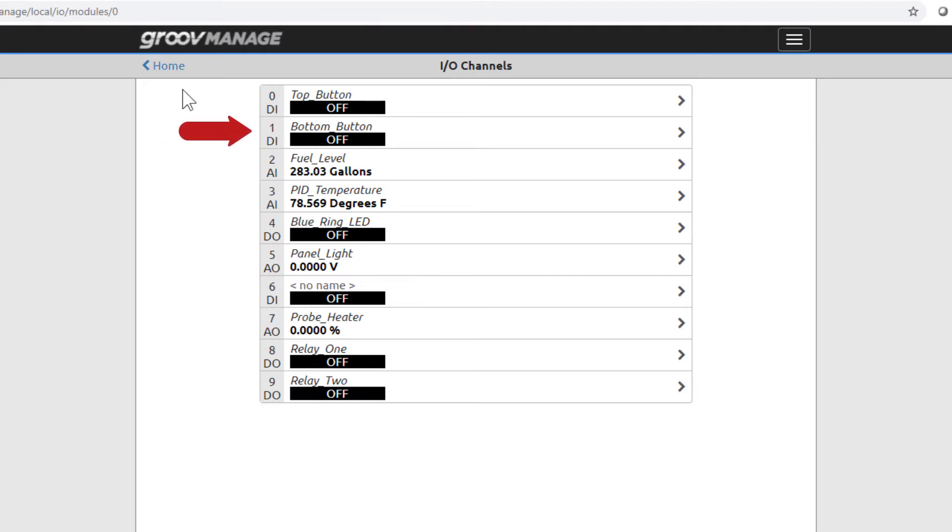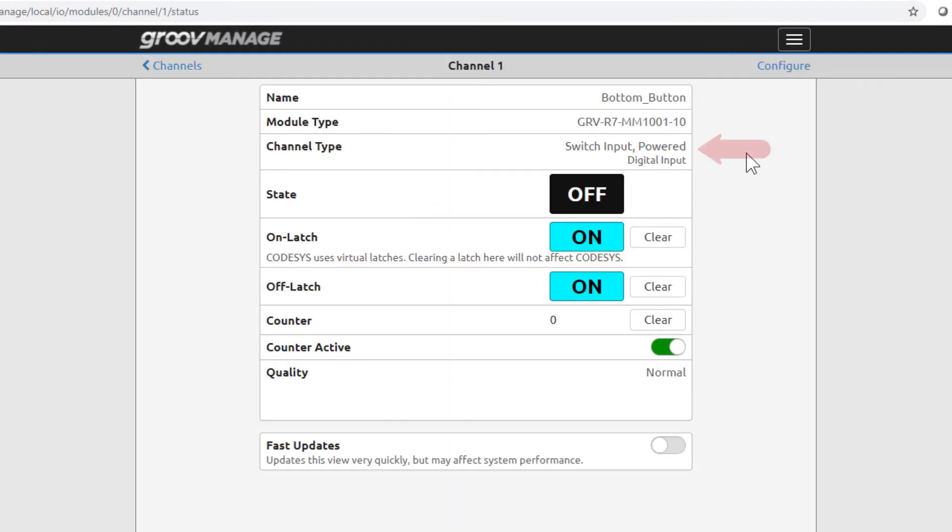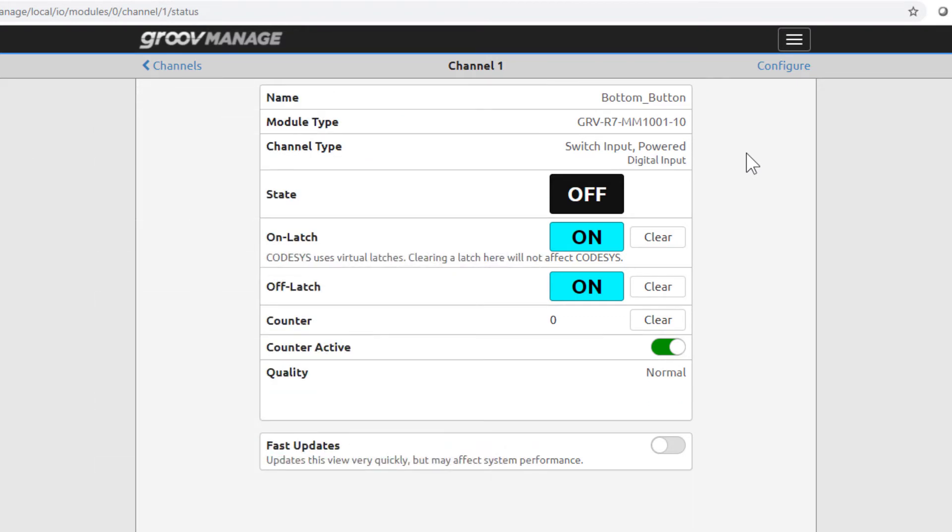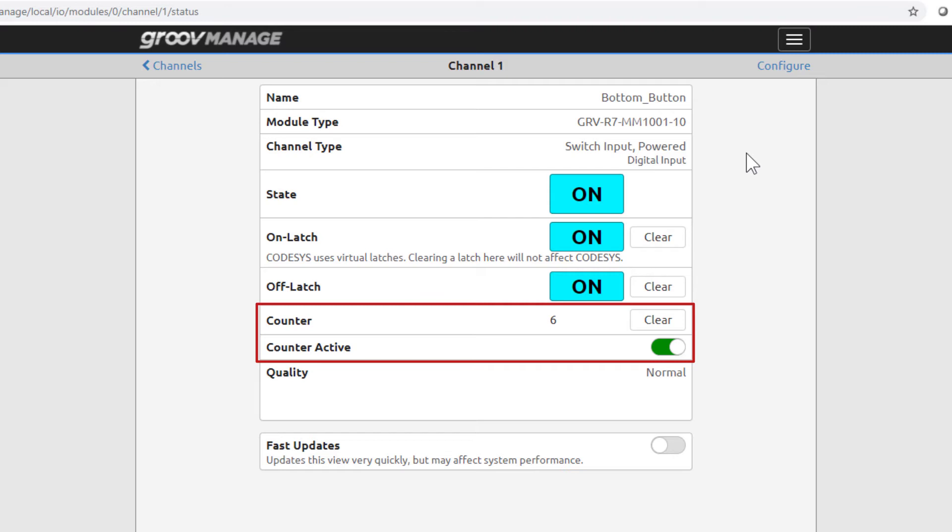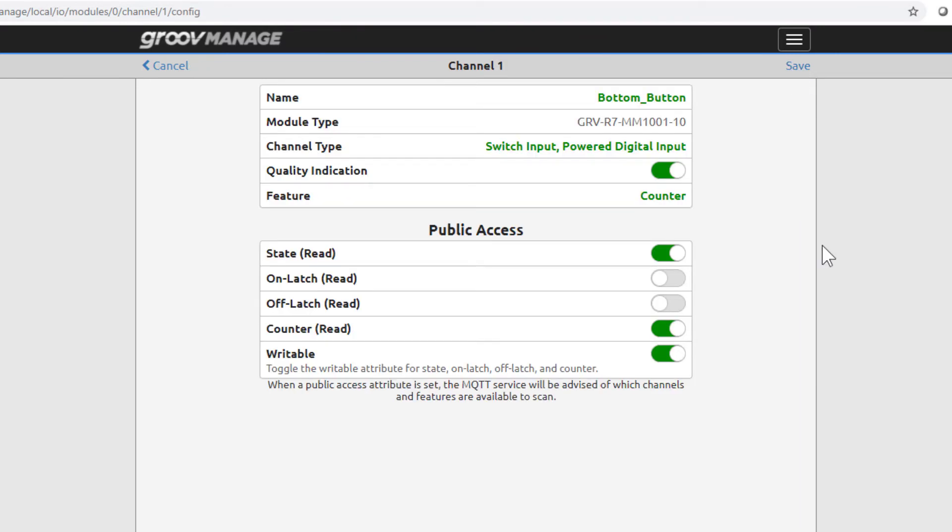Bottom button is a digital input, but let's take a look at what type it is. It's a digital input that's a powered switch input. This means the module provides the power to a dry contact switch. In your application, this can save you costs in wiring external power to the switch. The bottom button is a momentary button, meaning it stays on only as long as you press the button. It also has on and off latches. This input has been configured as a counter, meaning it'll keep track of the number of times the bottom button is pressed on and off.